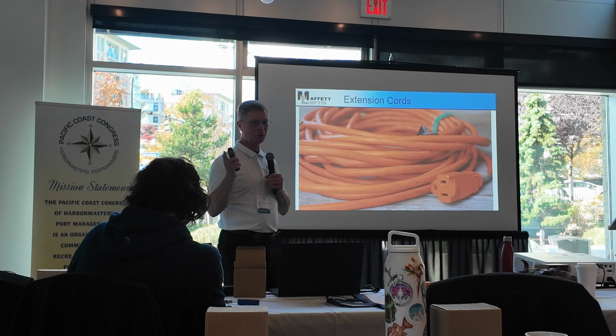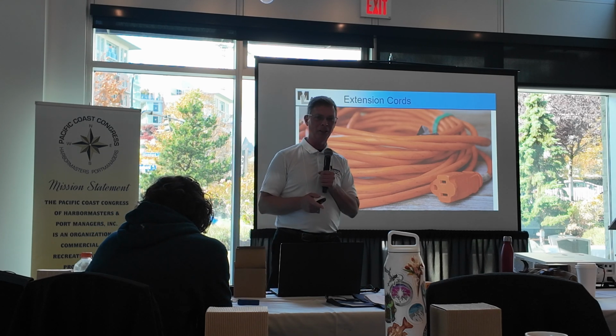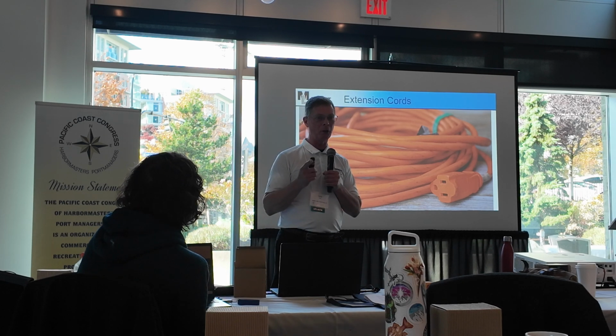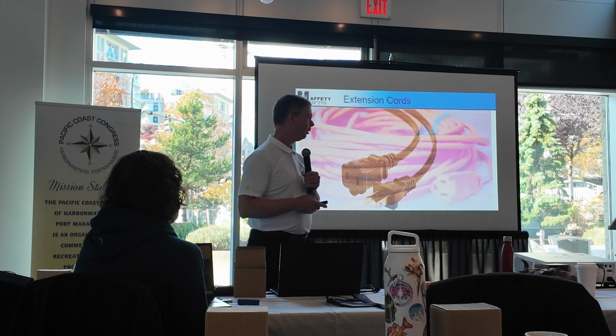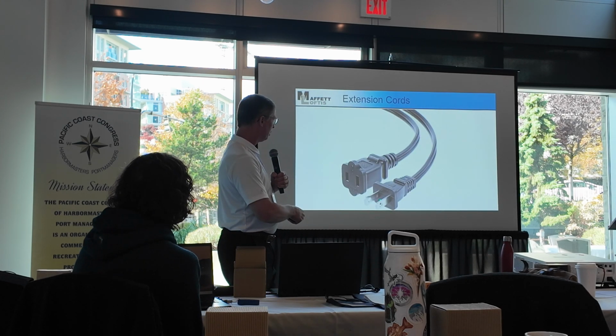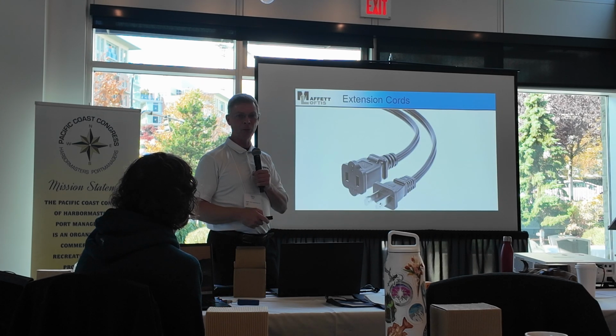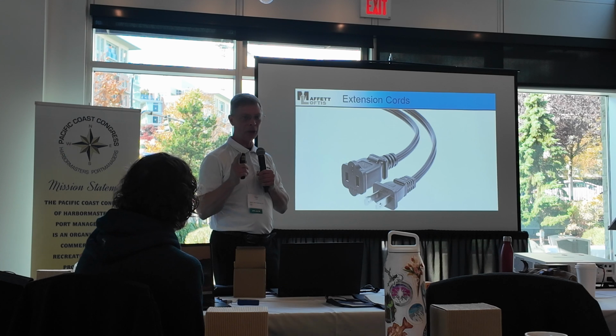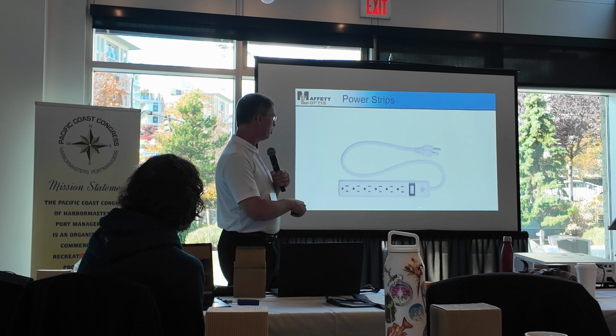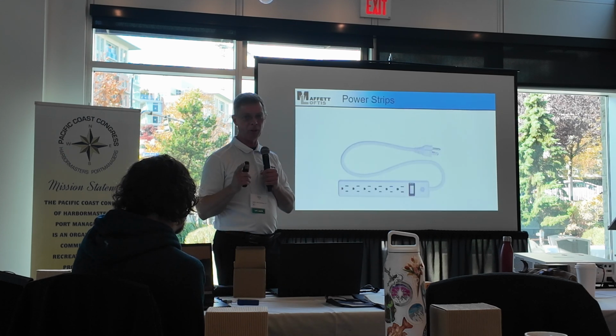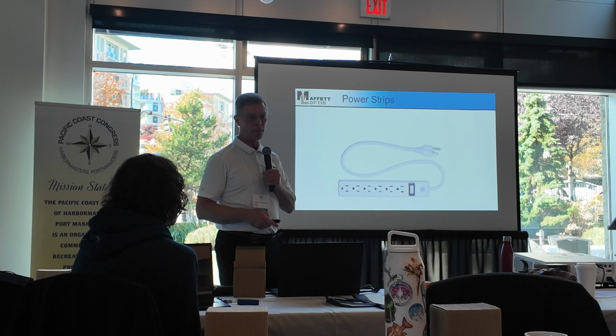Extension cords, are extension cords ever a good thing? They have their purpose, but they're not for permanent power. And I see this a lot. Is that a good thing on a marina? It's very temporary. No grounding wire, right? Don't let those on your marina. These are dry top only. Don't let them on your marina. They're not wet listed.